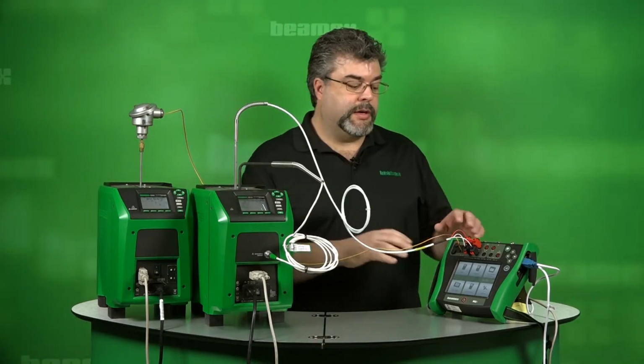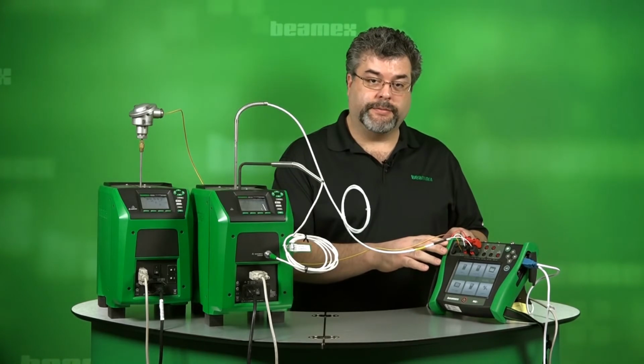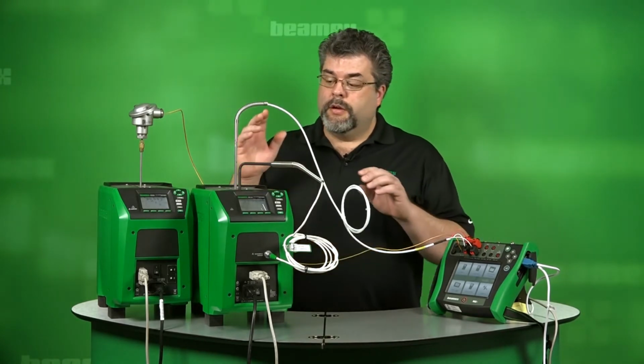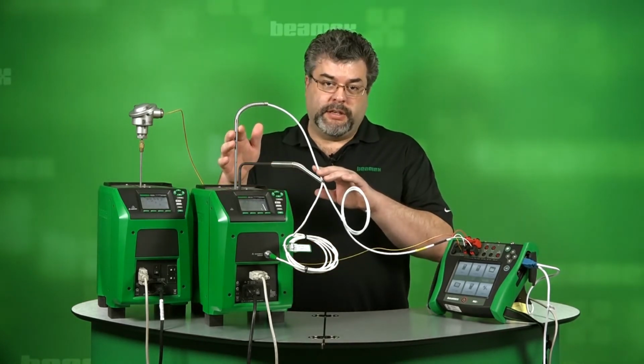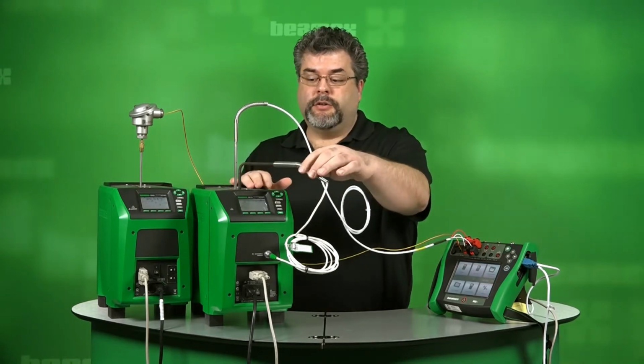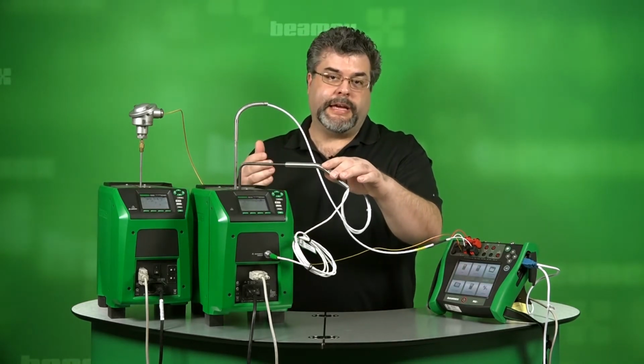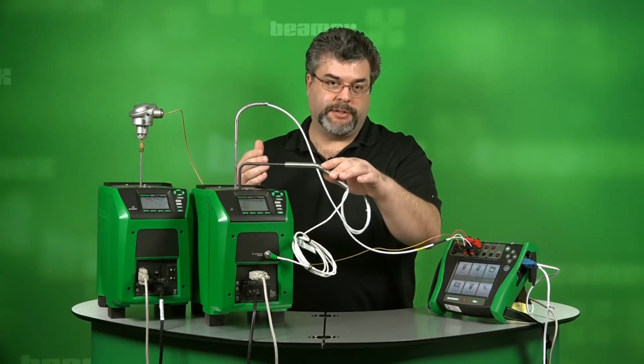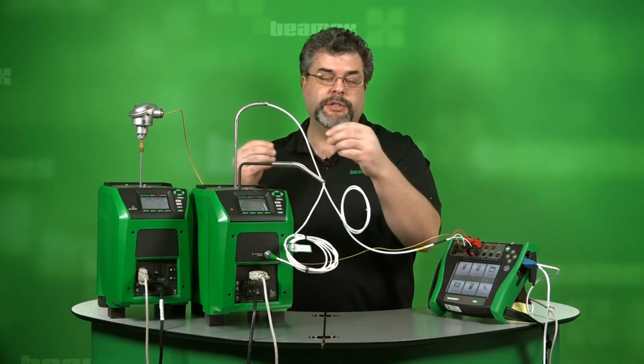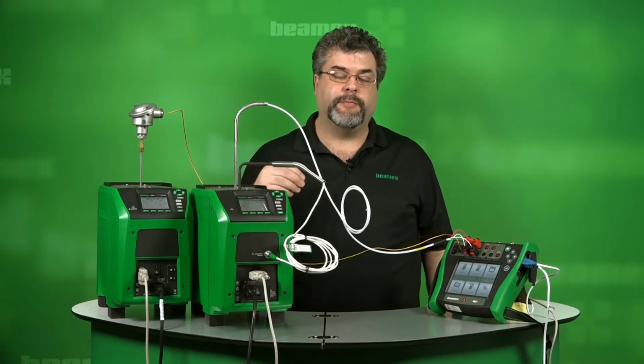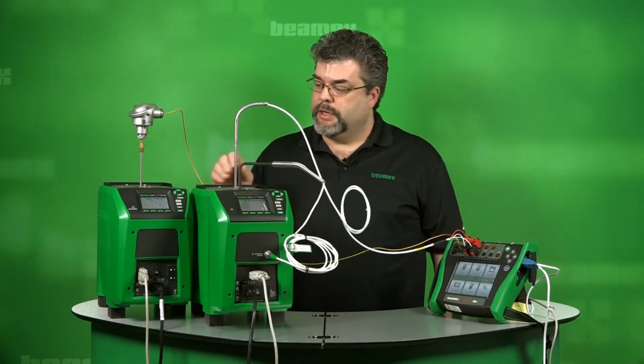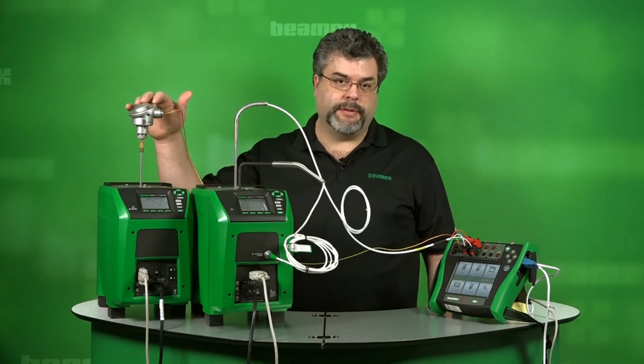I'm also using a Beamex MC6 calibrator. What we're testing is an RTD along with a high accuracy PRT reference sensor. This is increasing our accuracy over the dry block itself by about 10 times. In the high temperature block, we have a thermocouple that we're testing.